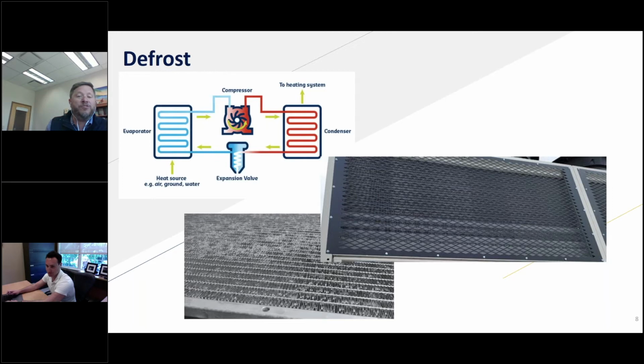When we see that happening, the air source heat pump is going to go into what we call a defrost mode. Essentially, we reverse the flow of the refrigerant. The refrigerant that was going to the condenser, the refrigerant to water heat exchanger, now becomes our evaporator, or our heat source. We do that so we can take that heat and send it through the air coil to warm the air coil above freezing temperature. That melts the frost and removes it from the coil, and we get back to where we should be from a heat transfer perspective, from a design perspective.